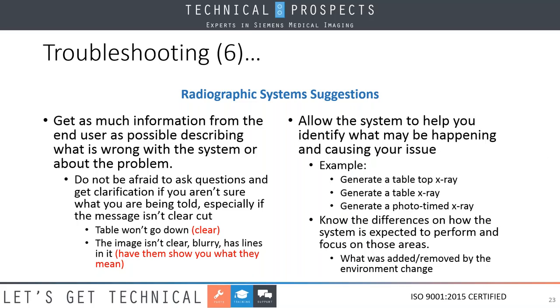All right. Second thing we don't do as engineers, we don't allow the system to help us find what's causing our problem. For example, I give you three different ways of generating an X-ray: a tabletop, a table, and a phototimed. Now, what you need to figure out and what you should be knowing is, what is the difference between each of these? For example, if I do a tabletop X-ray, I don't need to worry about a bucky and stuff. But when I do a table X-ray, now the bucky is in play, cassette sensing is in play, and other things. So now I'm looking for certain signals to be coming out of the table over to the machine. All right. These are typically manual shots, which I'll talk about here in a little bit.